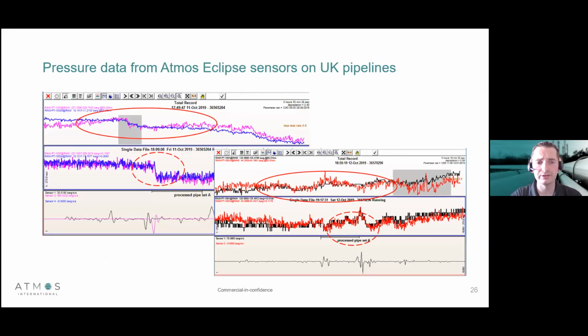Very briefly, these are 2 screenshots of an intrusive pressure sensor matched with a non-intrusive one. So if we just take the top left screenshot, the pink trend is non-intrusive pressure and the blue trend is intrusive pressure. And as you can see, they follow closely coupled, so we can get good levels of information and detail out of a non-intrusive pressure sensor.